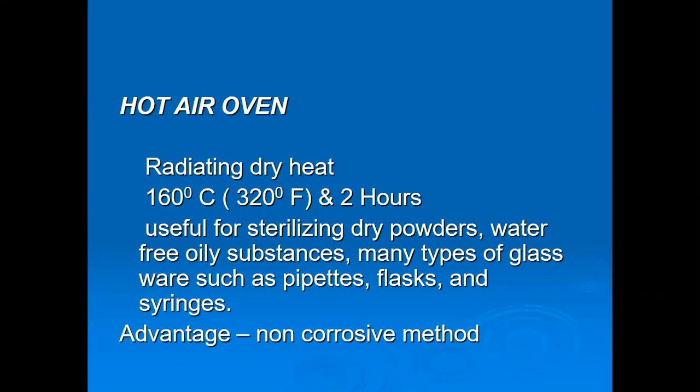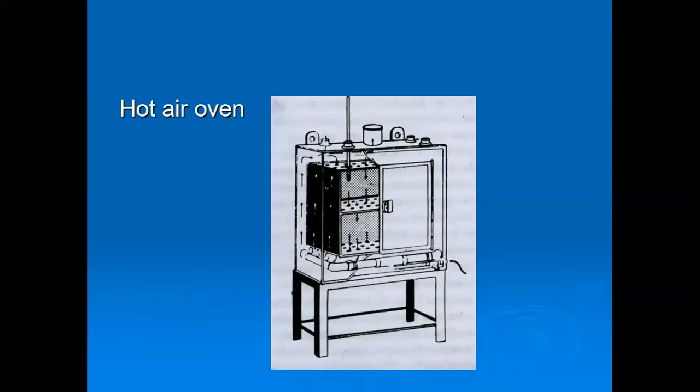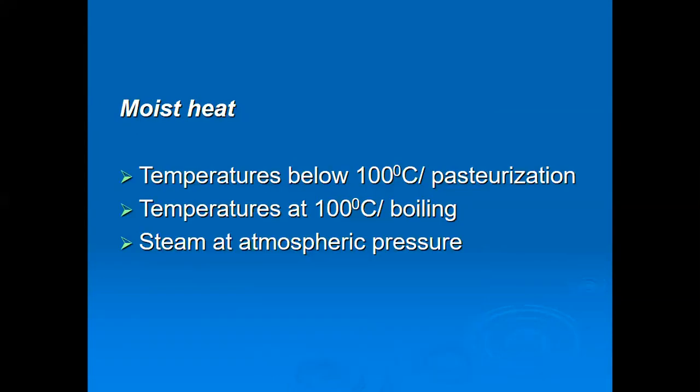Useful for sterilizing dry powders and other things. Please remember 160 degrees for 2 hours. Advantage, non-corrosive method. Hot air oven.